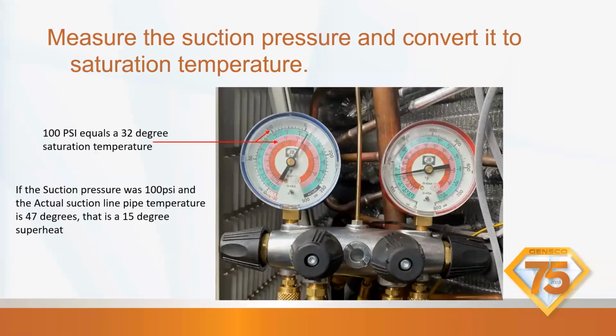So I just wanted to show you where that is on an analog set of gauges. Most of the digital gauges will display it automatically, but on your suction side, if you had 100 PSI in the lines, that's going to register 32 degrees saturation temperature. This 410A is in pink, R22 is in green, 404 is in red, but the pink one is what we're going to go off of. So at 100 PSI, our saturation temperature is 32. If we're at 125, we'd be at 42 degrees saturation temperature. So if the suction pressure was 100 PSI and the actual suction line temperature was 47, that is a 15-degree superheat. If our actual suction line temperature from our pipe clamp was 47, that would be superheated vapor. I just wanted to show that on a regular set of gauges.